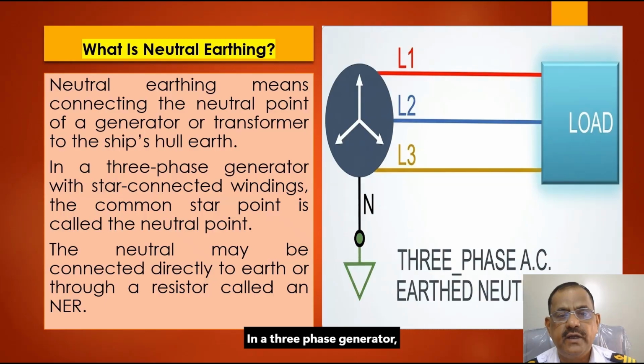In a three-phase generator, the windings are normally connected in star connection. The common star point is called the neutral point. This neutral can be connected directly to earth or connected through a resistor called an NER.